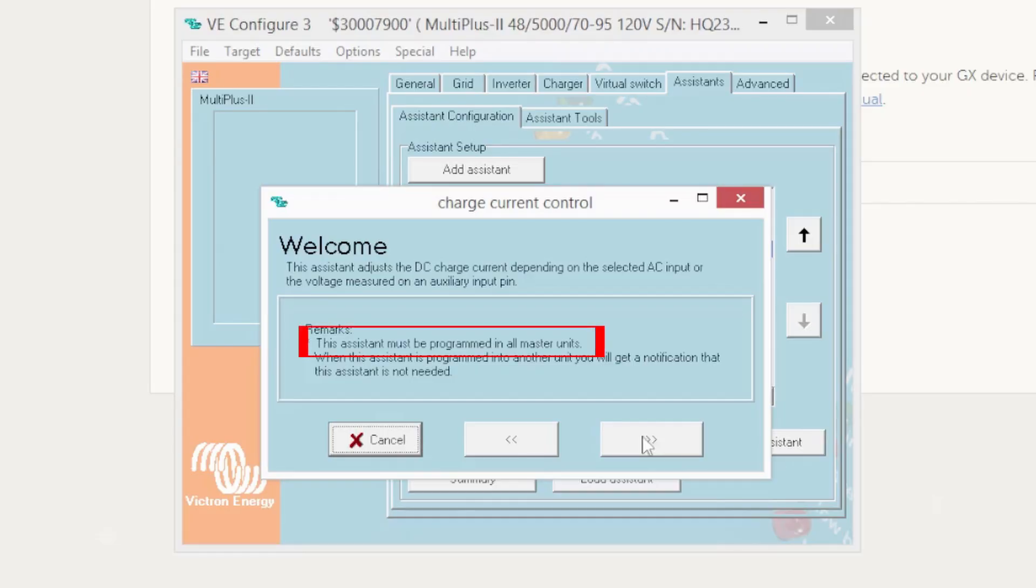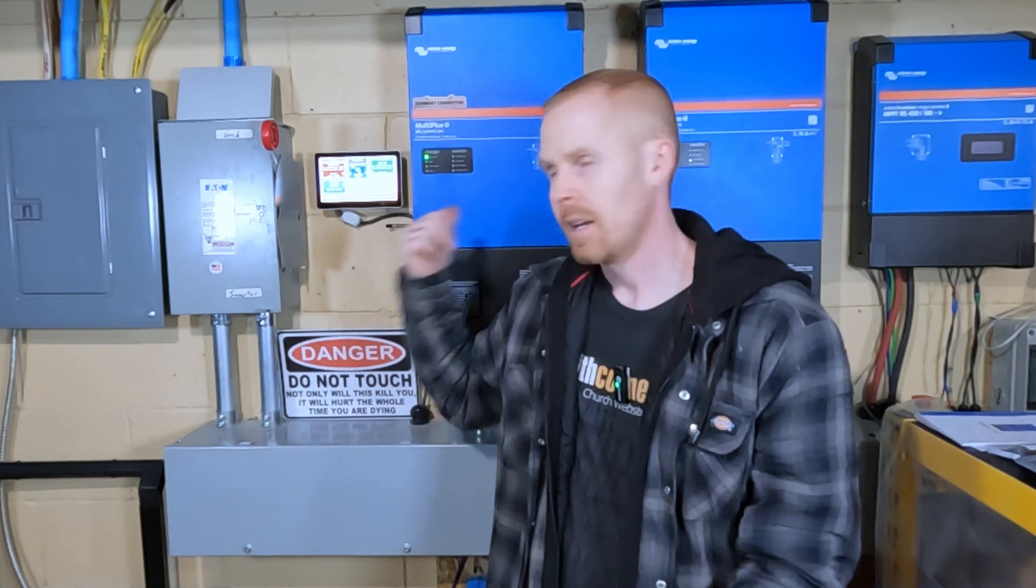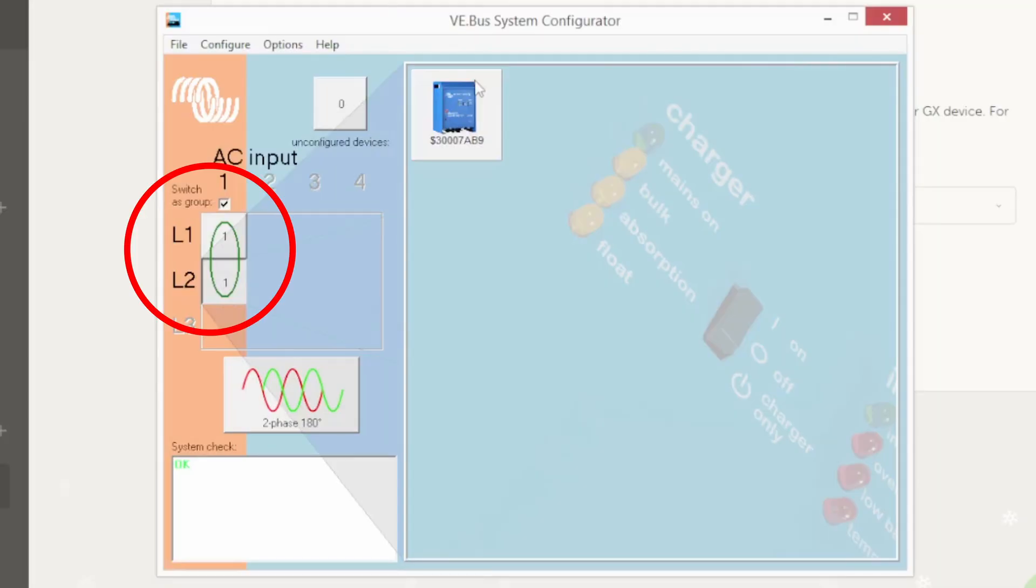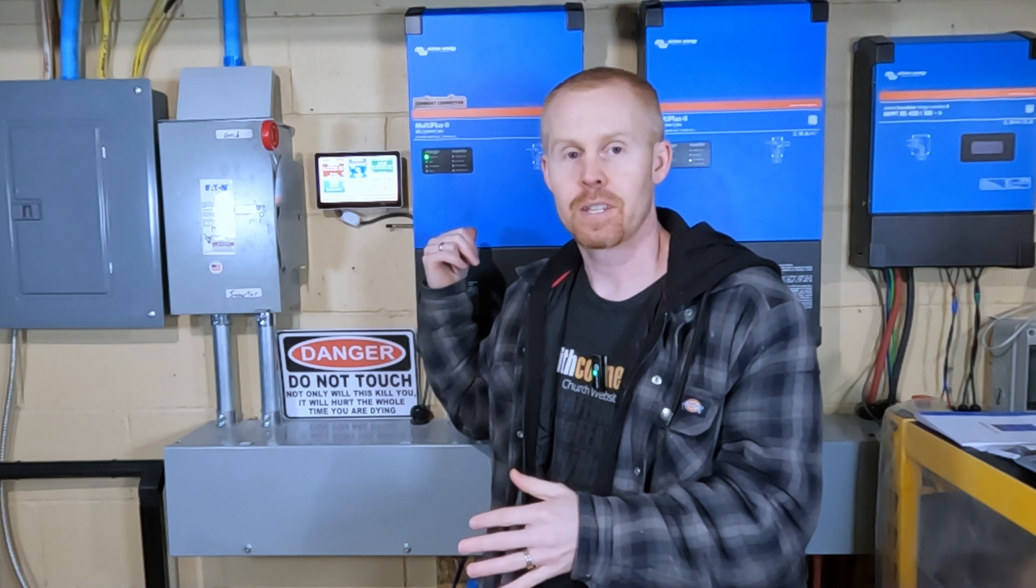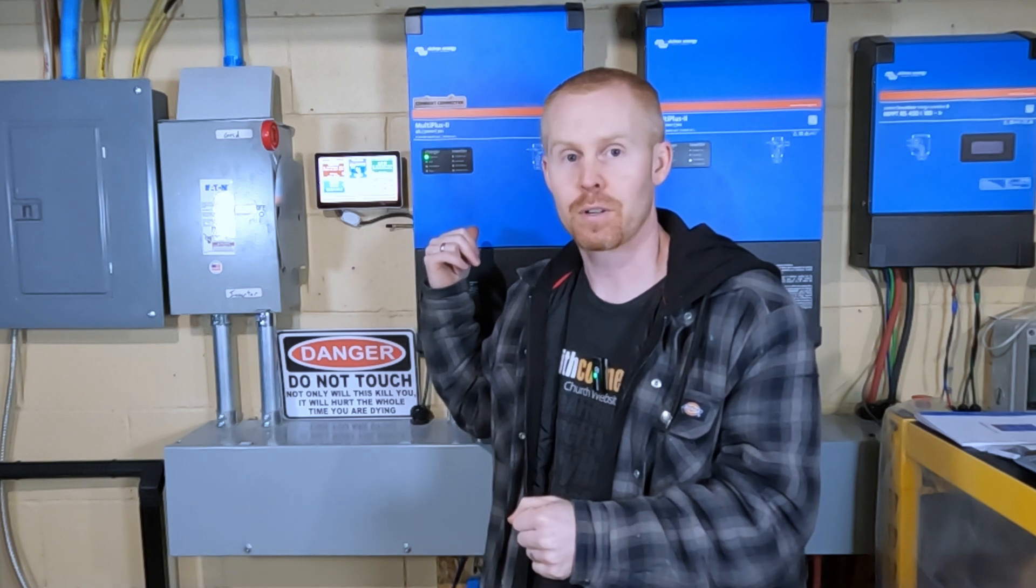And here's the big reason that I missed this step with the assistants. Looking at the charge current assistant, it says you only need to install this assistant on the master inverter. And my mind kept thinking leg one was the master and leg two was the slave. And it's not that way in this environment. They are each master inverters of their individual legs. So this is a master inverter for leg one. This is a master inverter for leg two.